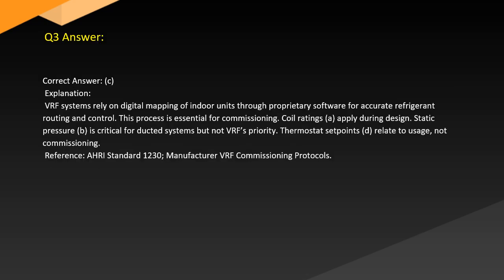Answer. Correct answer: C. Explanation. VRF systems rely on digital mapping of indoor units through proprietary software for accurate refrigerant routing and control. This process is essential for commissioning. Coil ratings, A, apply during design. Static pressure, B, is critical for ducted systems, but not VRF's priority. Thermostat set points, D, relate to usage, not commissioning. Reference: AHRI Standard 1230, and manufacturer commissioning protocols.